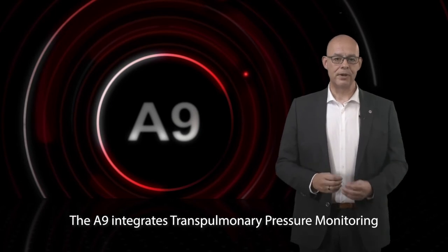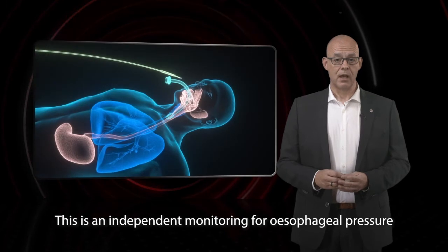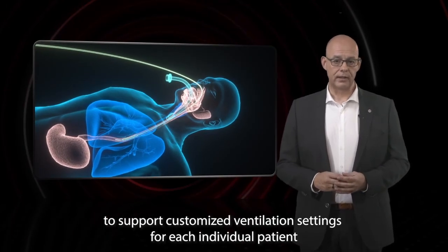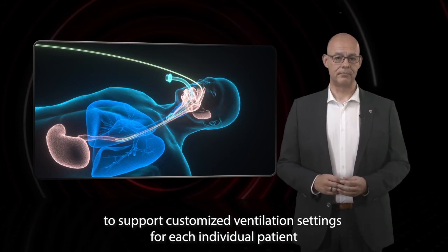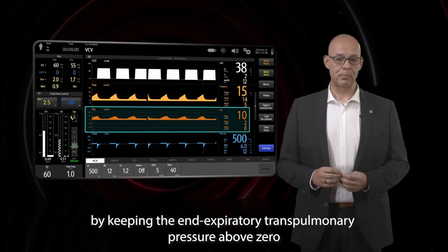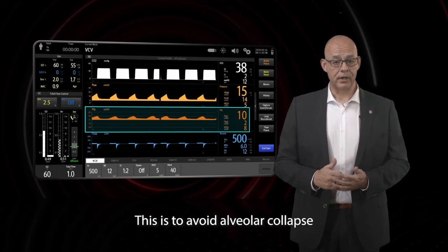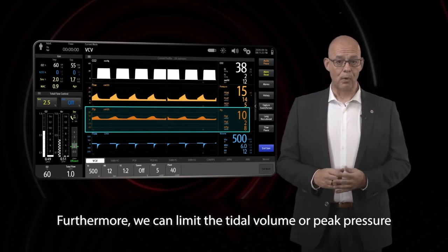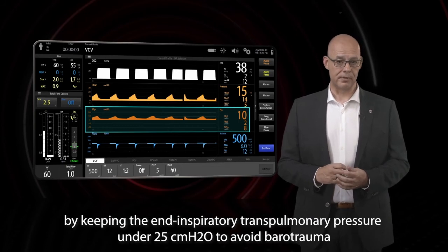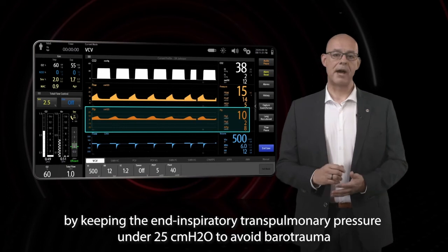The A9 integrates transpulmonary pressure monitoring — an independent monitoring for esophageal pressure to support customized ventilation settings for each individual patient. We can titrate the optimal PEEP by keeping the end-expiratory transpulmonary pressure above zero to avoid alveolar collapse. Furthermore, we can limit the tidal volume or peak pressure by keeping the end-inspiratory transpulmonary pressure under 25 cm of water to avoid barotrauma.